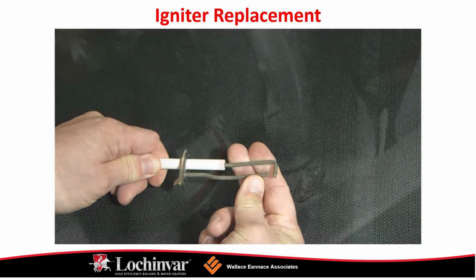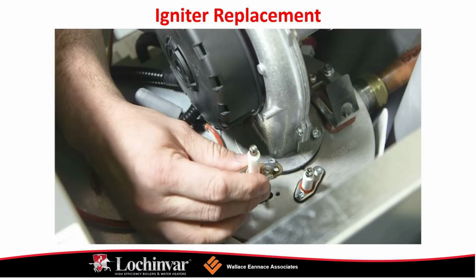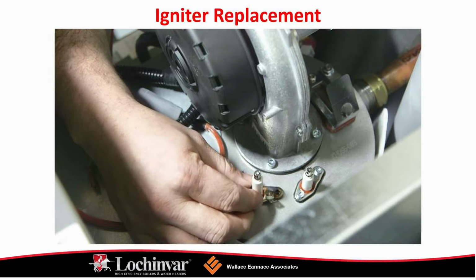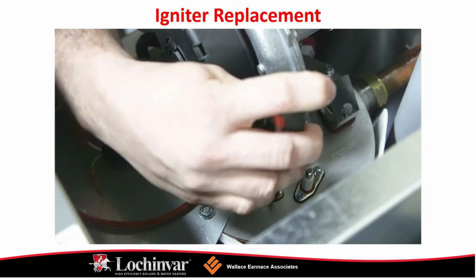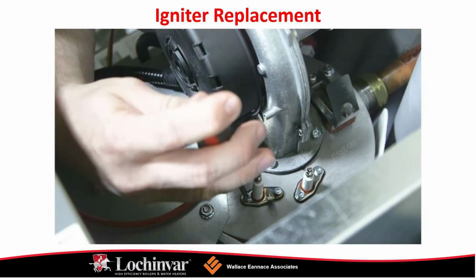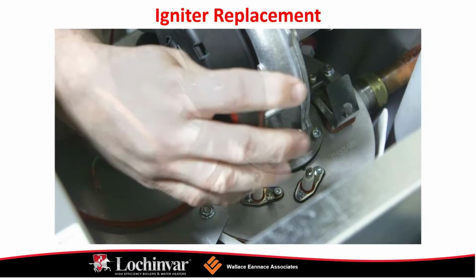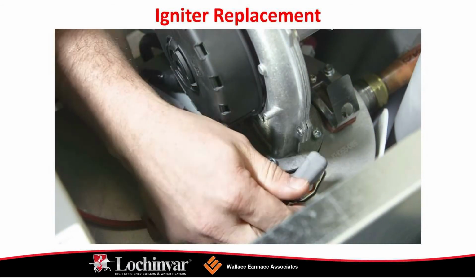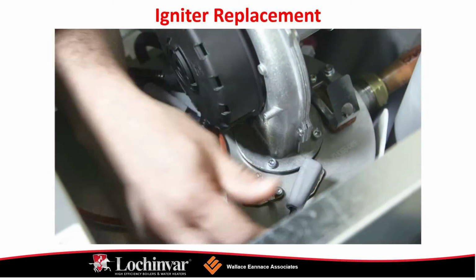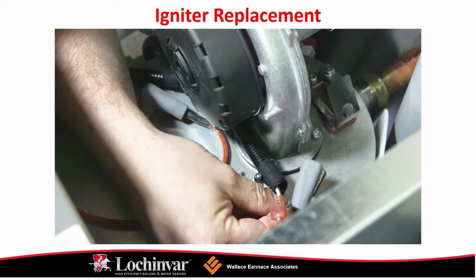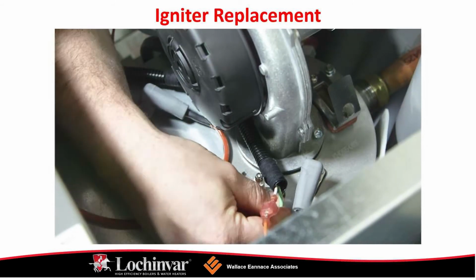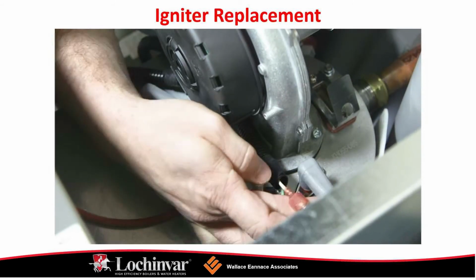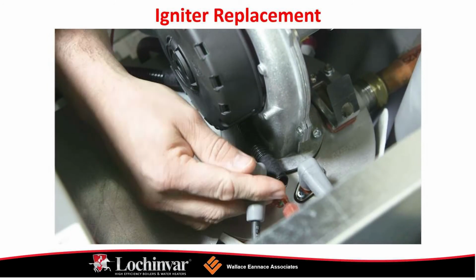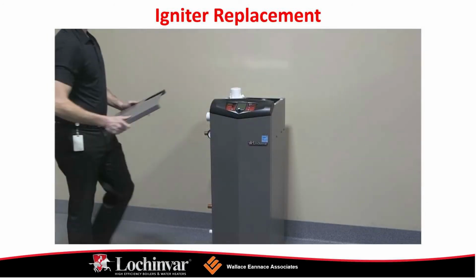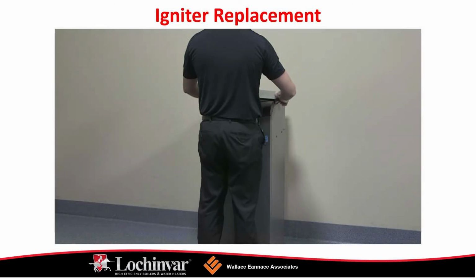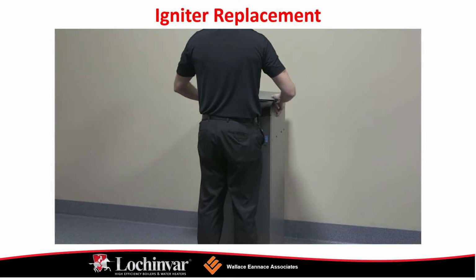Begin by removing the top access panel and lifting it up and away from the unit. Then remove the wires from the ignition probe, flame sensor, and ground terminal. Using a TX20 Torx driver, remove the 2 screws holding the ignition probe in place. You can now slide the ignition probe out of the combustion chamber door by lifting it up and away.